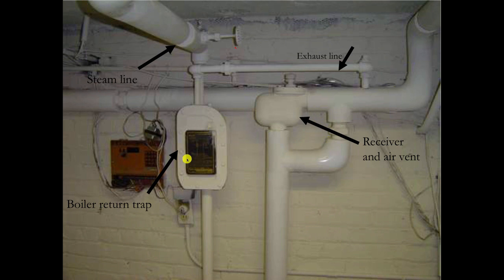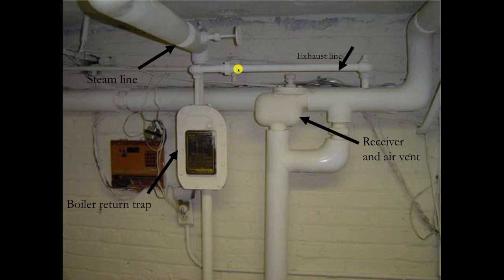The way to know whether it's working: when it's running, feel the steam line — it should be hot. This other line over here should be cold to the touch. If that line is hot, something's wrong. There should not be steam in that line.